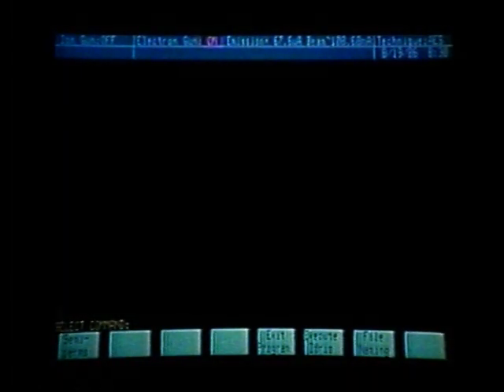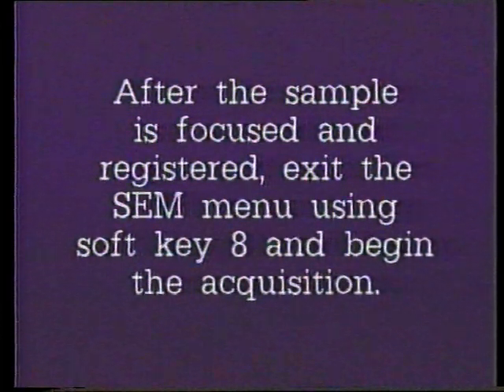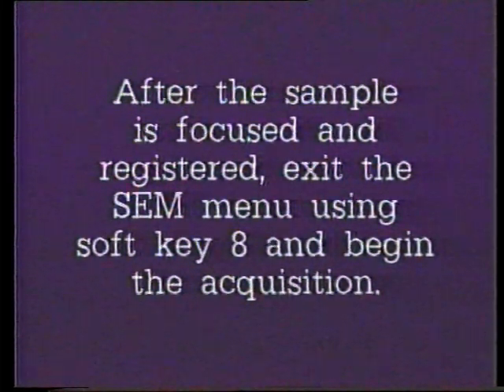Before we actually acquire the survey scans, we should go back to the TV image to make sure it is in focus and that we have proper registration with the mark on the TV screen. We'll enter the SEM menu, which allows us to access image shift using function key number 3. Using the arrows, we can shift the sample back into proper position with the registration mark. Once lined up, we can also use the fine focus to ensure the best focus possible. Now that the sample is focused and registered, we can exit the SEM menu using soft key number 8 and begin our acquisition.